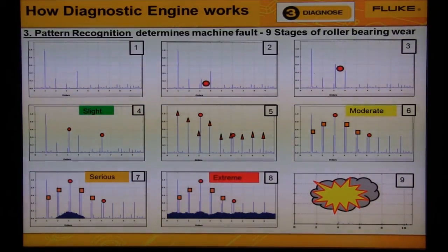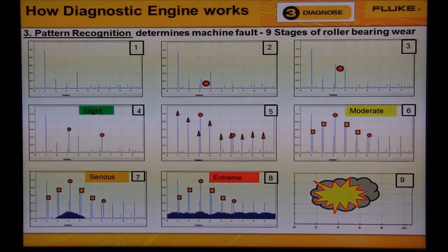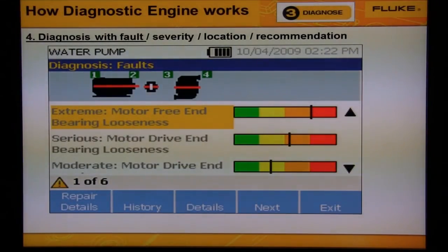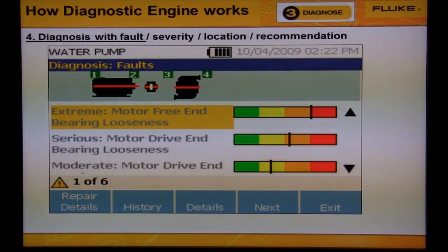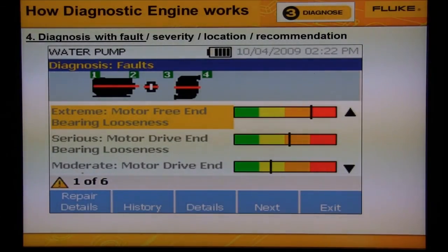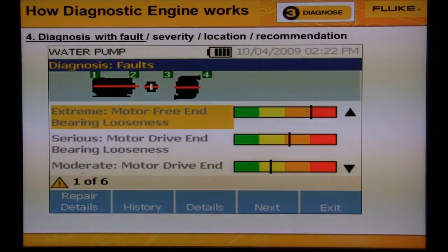You can watch the machine fault go from slight to moderate to serious to extreme. At the last step, we see the results of the diagnostic report. The diagnostic engine found the shaft speed, developed a baseline, compared the exceedances to 4,700 rules, then gave a report with the fault severity, location, and recommendation.